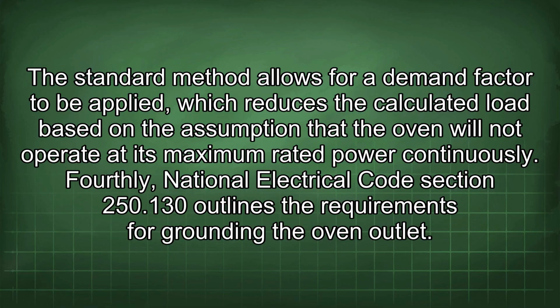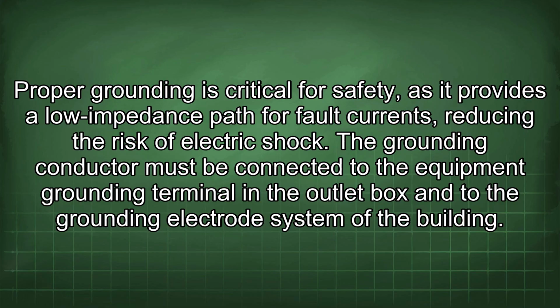Fourthly, National Electrical Code Section 250.130 outlines the requirements for grounding the oven outlet. Proper grounding is critical for safety, as it provides a low impedance path for fault currents, reducing the risk of electric shock. The grounding conductor must be connected to the equipment grounding terminal in the outlet box and to the grounding electrode system of the building.